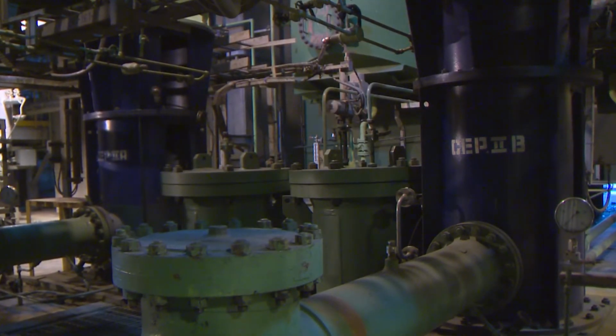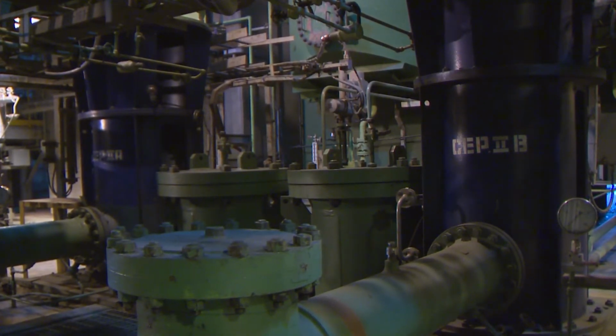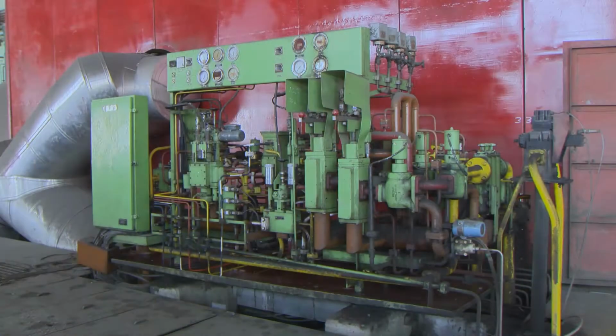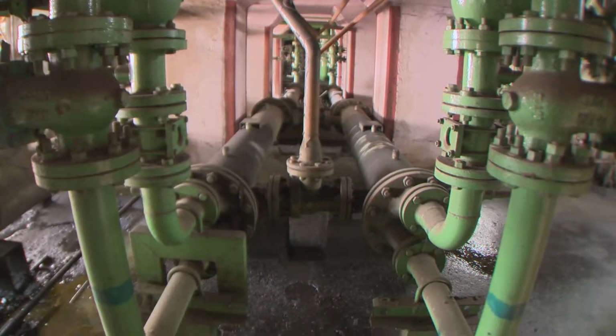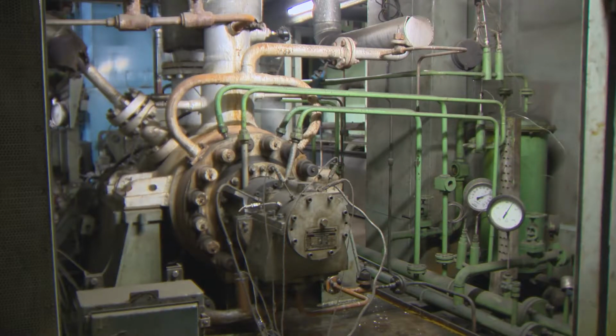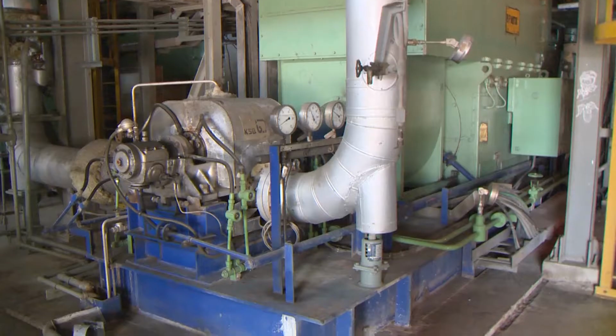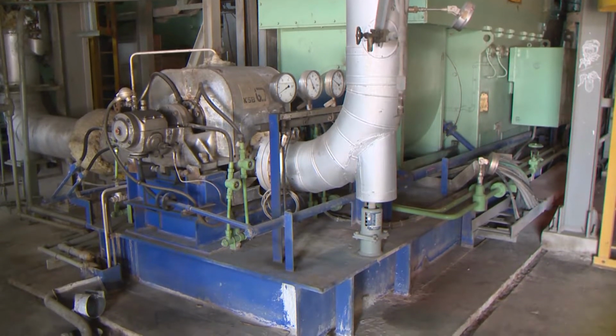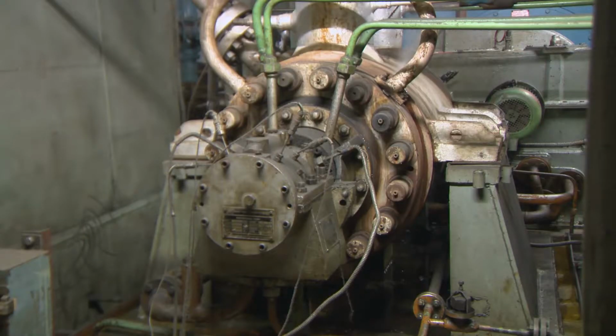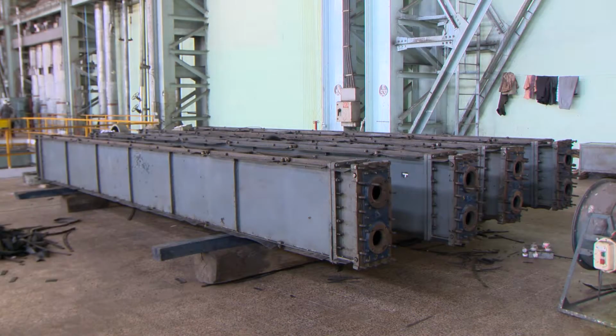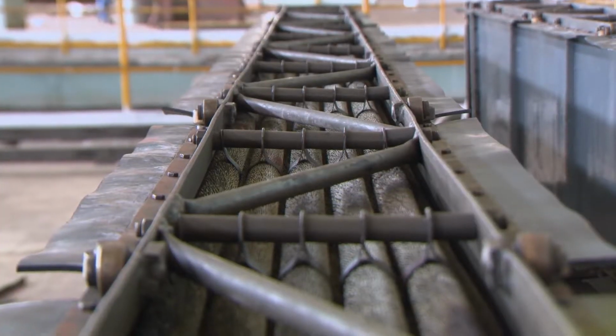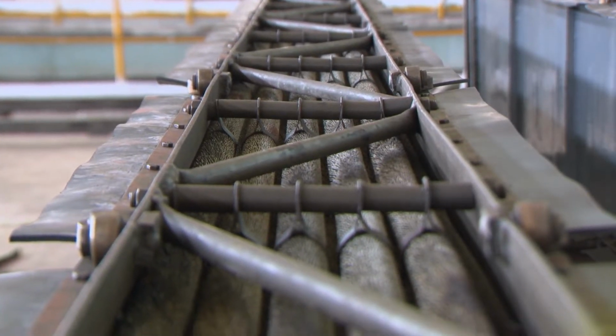Turbine zone, lube oil cooler in condensate extraction pump, governing oil system, working oil cooler, mechanical seal cooler, seal box cooling in booster pump and main pump. In generator zone, hydrogen gas coolers.